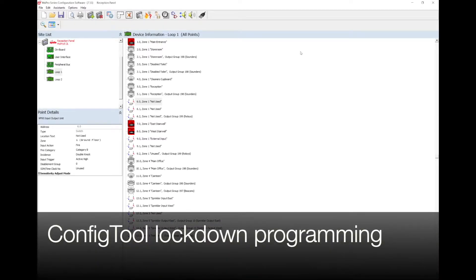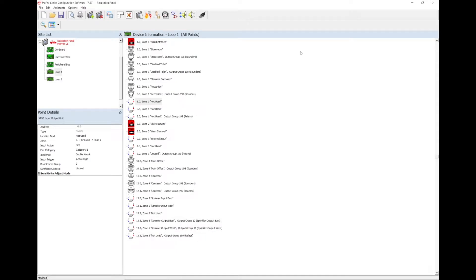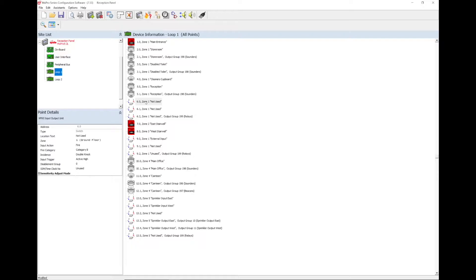Locate a spare input to be used for the lockdown input. This could be a manual call point, a key switch, or an input on an IO module on the loop. On this config file, there is a spare input on loop 1 at address 6.